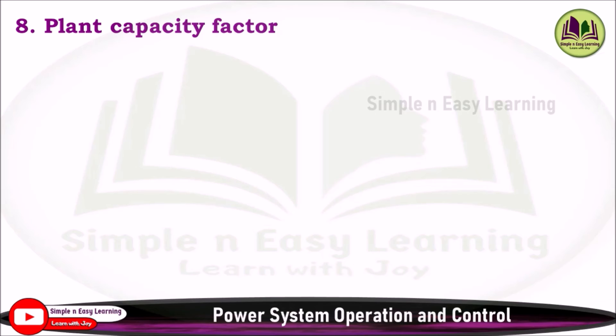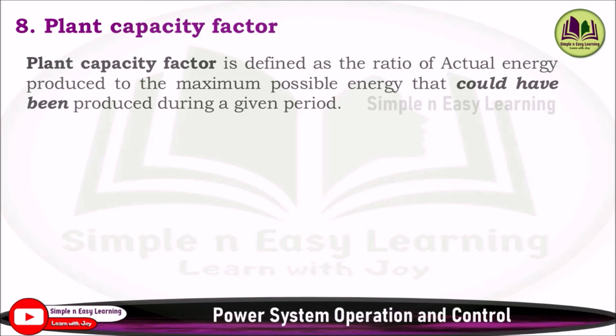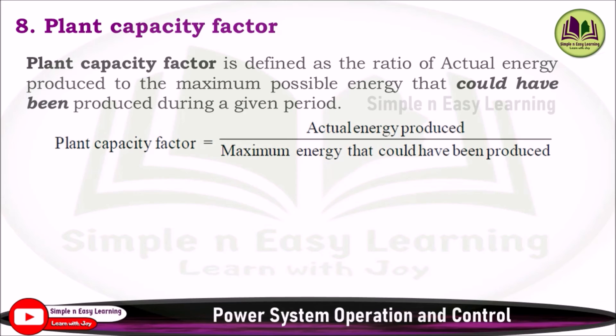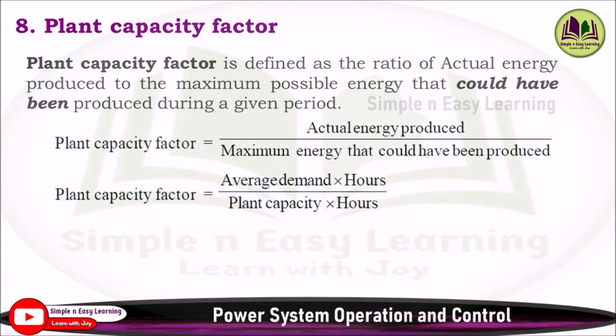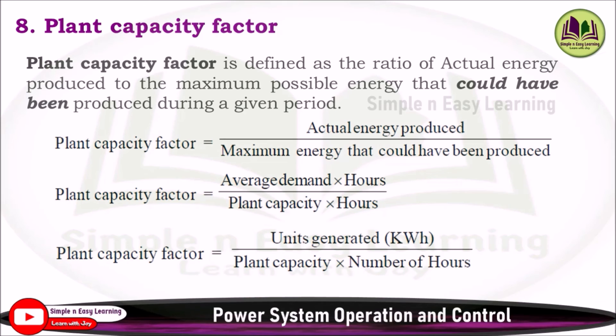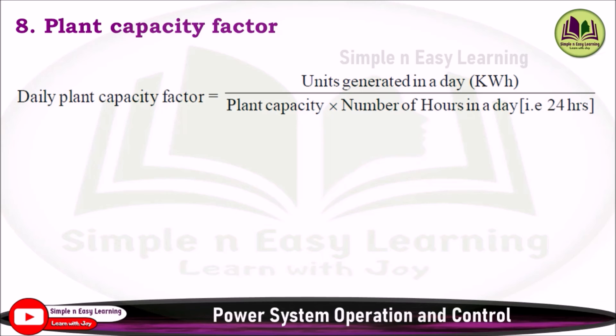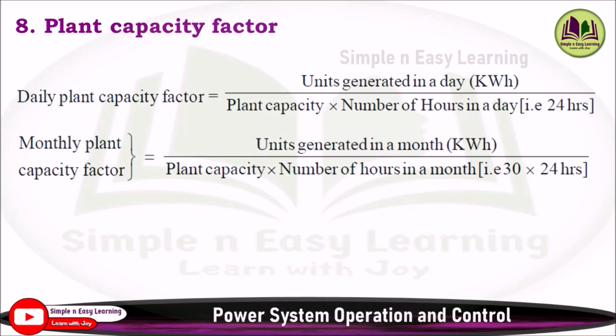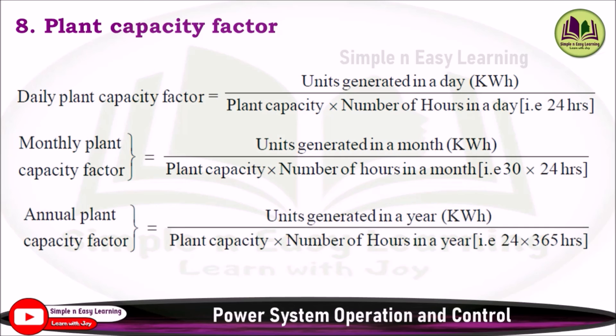Eighth: plant capacity factor. It is defined as the ratio of actual energy produced to the maximum possible energy that could have been produced during a given period. Plant Capacity Factor = Actual Energy Produced / Maximum Possible Energy = (Average Demand × Hours) / (Plant Capacity × Hours) = Units Generated / (Plant Capacity × Number of Hours). This applies for daily (24 hours), monthly, and annual plant capacity factor.